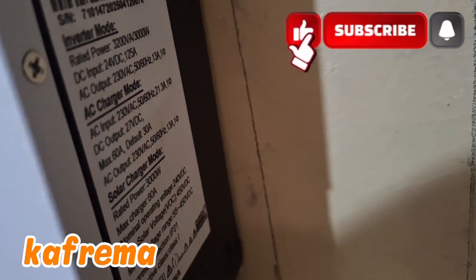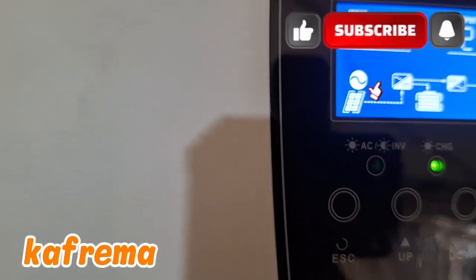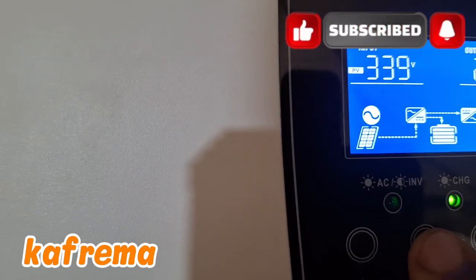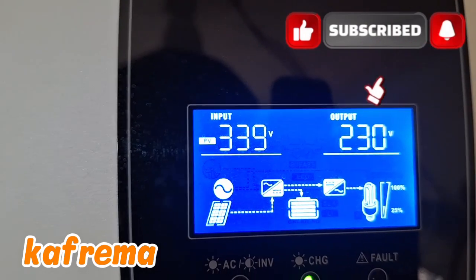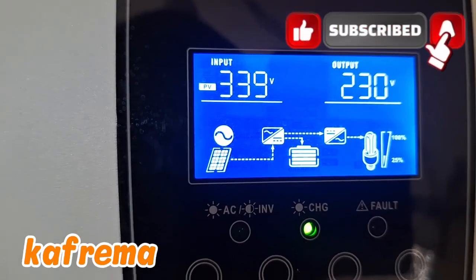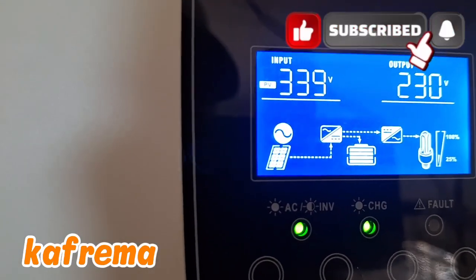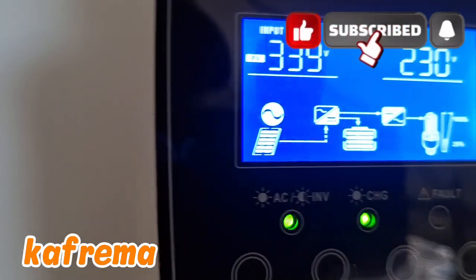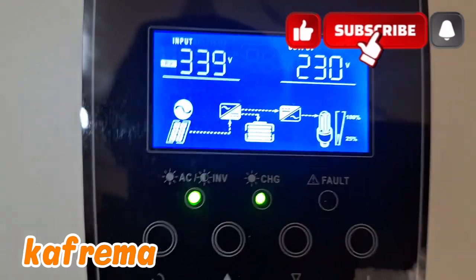So they are 450 volts. The voltage getting here should be less than 450 volts DC, which will go inside the inverter. Right now, from the PV we are getting 339 volts. You see it is below the 450, so we are good to go. Although right now the system is not charging because the batteries are already full. If you do the right calculation of your battery bank, it will be full by 11 because it will require only 5 or 6 hours of sunlight with no cloud cover.